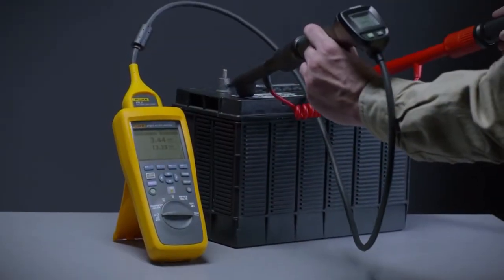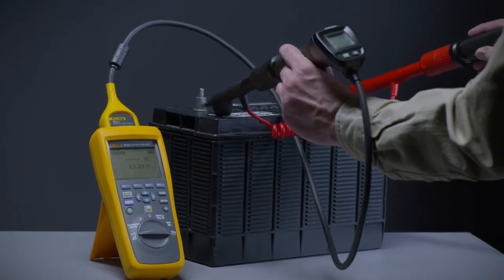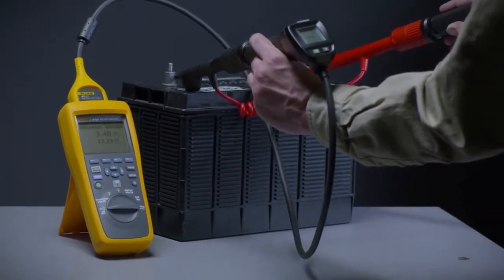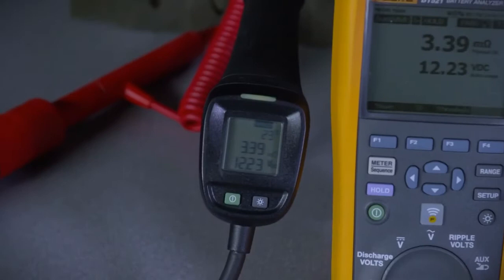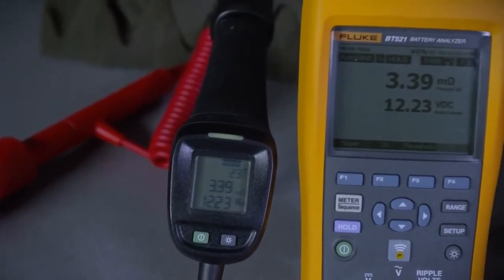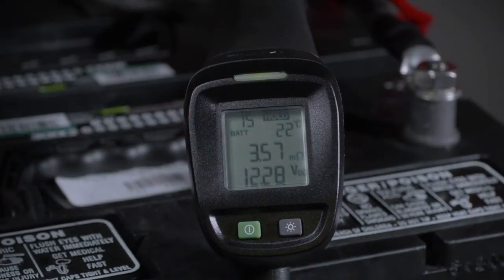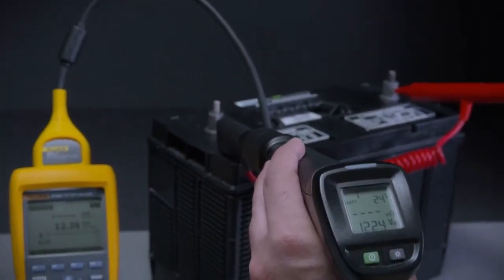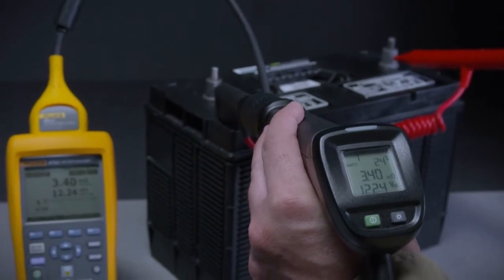One of the most significant improvements with the Fluke battery analyzer is the addition of intelligent test probes. The BTL21 intelligent test probe has the ability to indicate voltage as well as other readings such as milliohms and temperature right on the integrated LCD display, eliminating the need to refer to the main unit to verify measurement results.